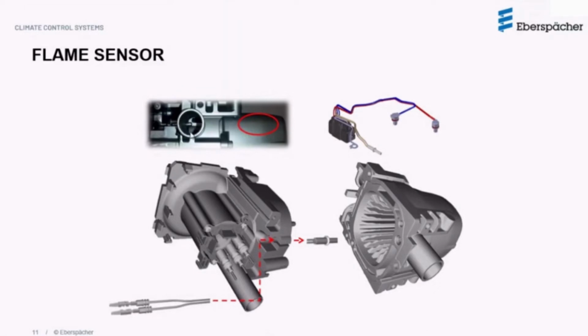That way it's able to get a much more optimized measurement. What has changed is that in the past, this sensor would be in a position where it was almost surrounded by cold coolant circulating around the heat exchanger, and the cold coolant would influence the temperature rise of the flame sensor, and thereby play a huge part in the successful start of the heater. So in the third generation heater, they have made a concentrated effort to move it back and separate the coolant jacket from the exhaust port. Now on the new heaters, this flame sensor is under no influence by the cold coolant circulating around, which automatically means much higher reliability.